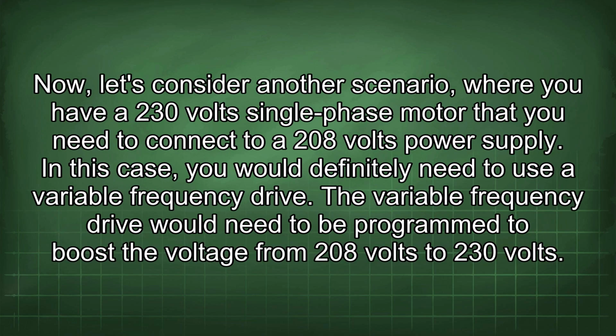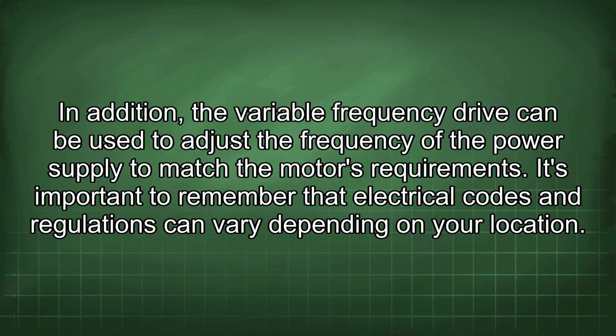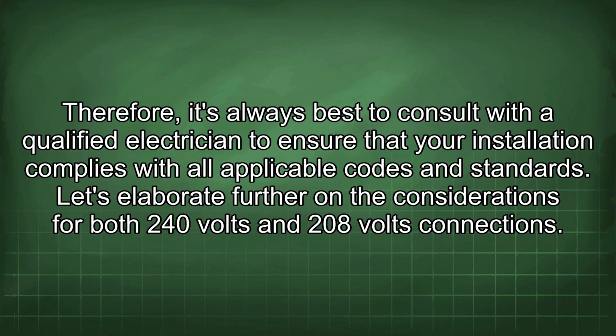Now let's consider another scenario where you have a 230 volt single-phase motor that you need to connect to a 208 volt power supply. In this case, you would definitely need to use a variable frequency drive. The variable frequency drive would need to be programmed to boost the voltage from 208 volts to 230 volts. In addition, the variable frequency drive can be used to adjust the frequency of the power supply to match the motor's requirements. It's important to remember that electrical codes and regulations can vary depending on your location. Therefore, it's always best to consult with a qualified electrician to ensure that your installation complies with all applicable codes and standards.